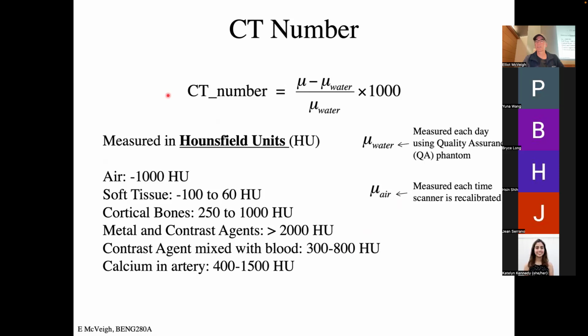Okay, so CT numbers. When we're doing our reconstruction, the thing that comes out, and to this day, on the unit are pixel values that are in Hounsfield units. And the way you create a Hounsfield unit image is you take the mu value for that voxel that you're interested in, and you say, well, what number am I going to display? I've got this mu value. What number should I display on the scanner? And in the 70s, when they were making all this stuff up, they were probably using like 12-bit numbers or something like that to do this.